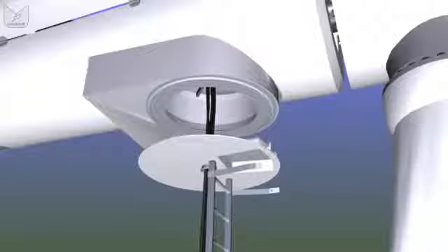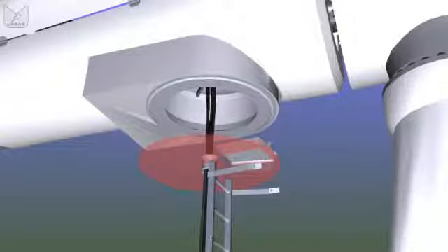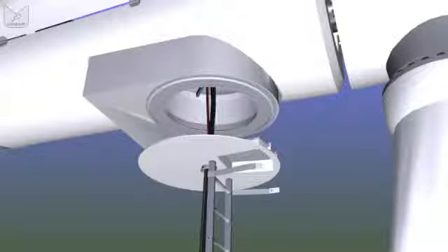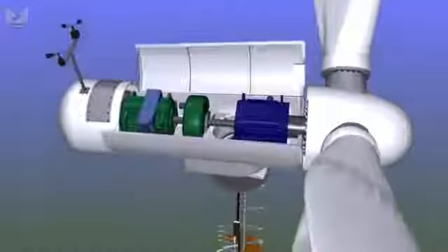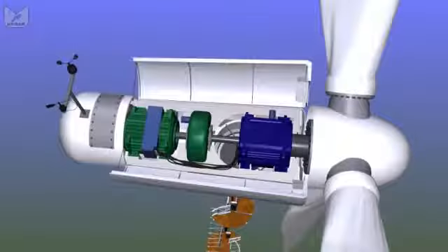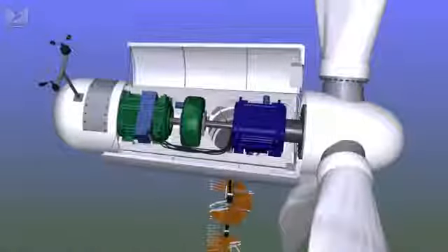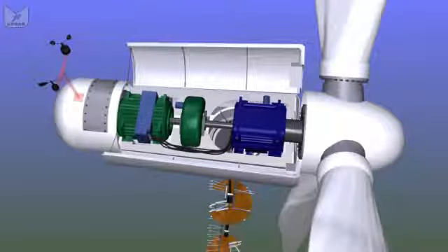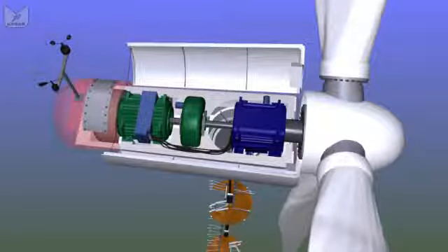Just above that we have the yaw ring with the bearings that allow the nacelle and the rotors to rotate around to face the wind. And this sealed platform acts as a bit of fire protection, also avoids people falling back down the tower, because at the top of the nacelle we simply have a hole through which we climb. And the nacelle in this case is a vaguely tapered tube. At the back we have the wind sensors, which give us speed and direction and allow the turbine to face into the wind and to change the angle of the blades.